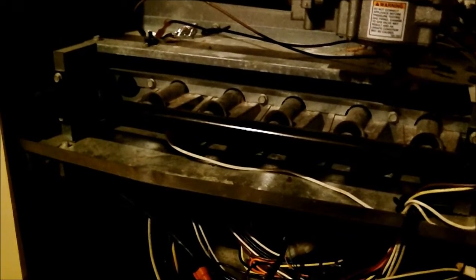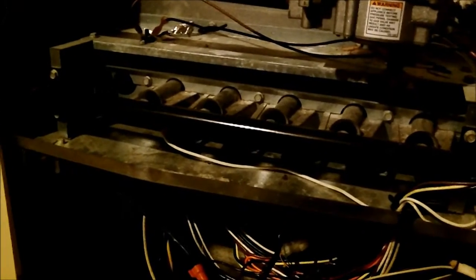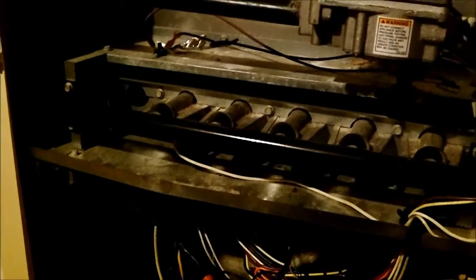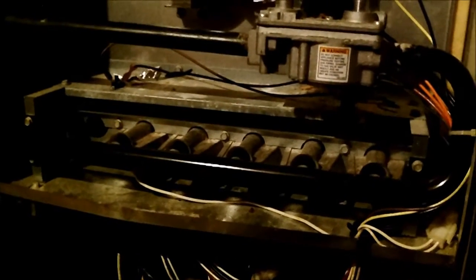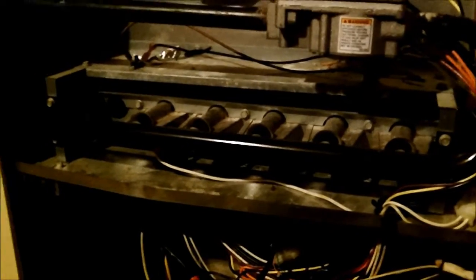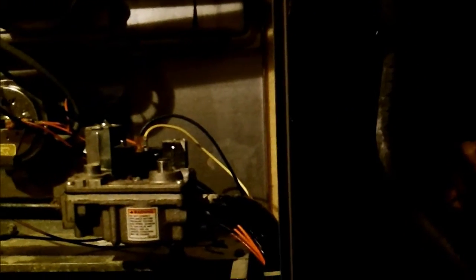What happens is if you run power over to the fan, it backfeeds through the thermostat and sends the outdoor unit on. So we're just going to put a lockout relay for the outdoor unit and let the humidistat bring the fan on to get the most out of your humidifier. The way it shows to be wired up from the instructions, it only comes on when the heat is running, but if the call for heat is over and you're still dry in the house, what's the point in having a humidifier installed if it's not going to continue to run?